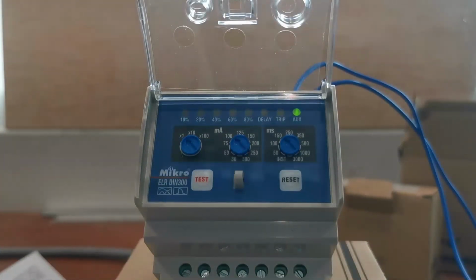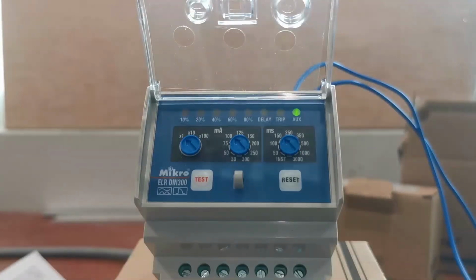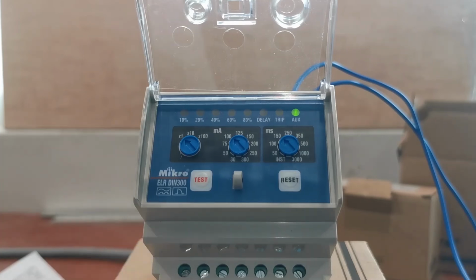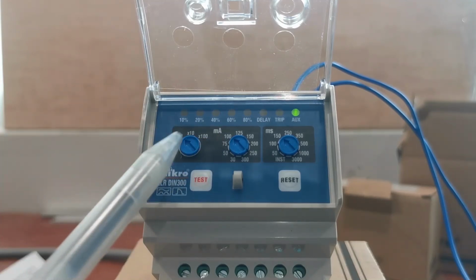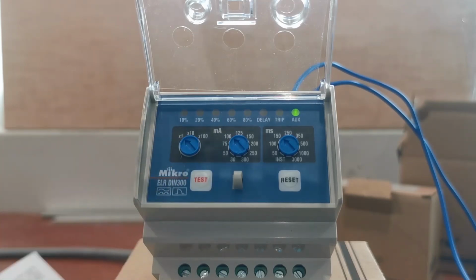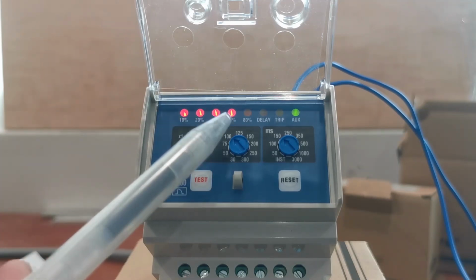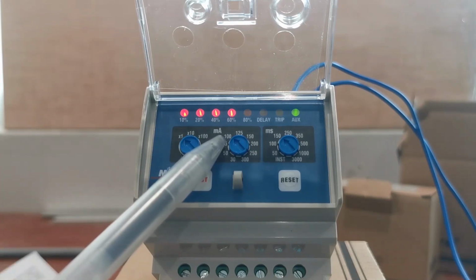An earth leakage relay is slightly different from a normal overcurrent and fault relay. The difference is, if I'm setting 100 milliamps, this relay will trip within 85% to 100% of your setting, meaning it will trip when the leakage current detected is above 85 milliamps to 100 milliamps and above. Currently, my setting is 100 milliamps. For this demonstration, I will inject 60 milliamps while my setting is 100 milliamps, which is shown here, 100 milliamps and multiplier of 1. I will inject it now. As you can see, the display shows 60%, which is 60% of your setting, indicating 60 milliamps.